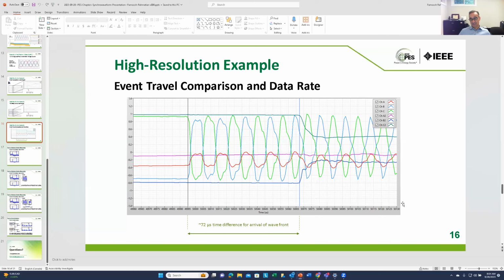For megahertz sampling, definitely not resistive. Resistive sensors and the secondary wiring do not have the bandwidth. Even in kilohertz, they have a very hard time. Most resistive dividers, even at distribution, by the time you pass 200, 300, 400 hertz, have significant error in terms of ratio. The lower the output of the resistive dividers, and if they're of special non-inductive type, they can give you more bandwidth. But most typical cheaper outdoor resistive dividers are not those special low inductance types. By the time you get to a few kilohertz, resistive dividers are not there. You could have RC dividers, resistive capacitive, which are more lab and slowly coming to the field. And by the time you get to a few tens of kilohertz, even they have a hard time.